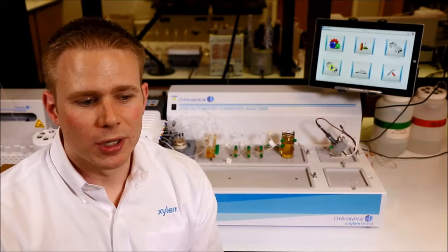OI has been really the leader in cyanide analysis for the last 20 years, and this is our latest generation of instrument really designed to focus on user experience and making instrumentation like this simple to use. Our calibration curves can easily include 4 orders of magnitude, and the methods developed on this platform for both cyanide as well as analytes like nitrate, phosphate, phenols, or ammonia are all designed to comply with EPA, ASTM, ISO, or standard methods.